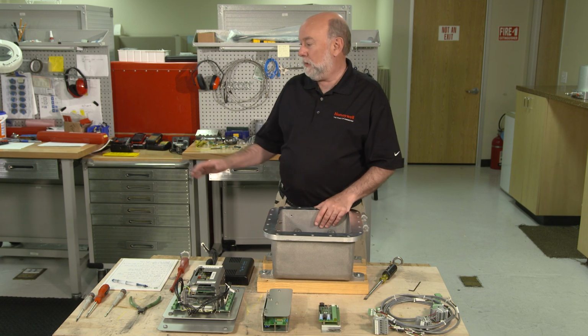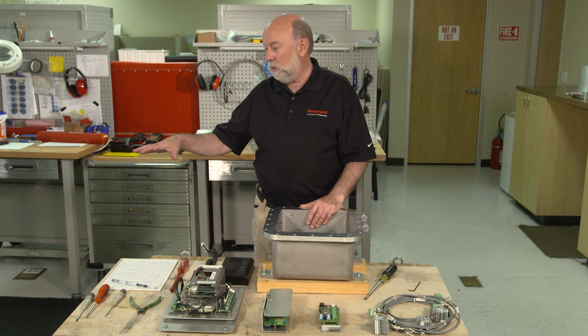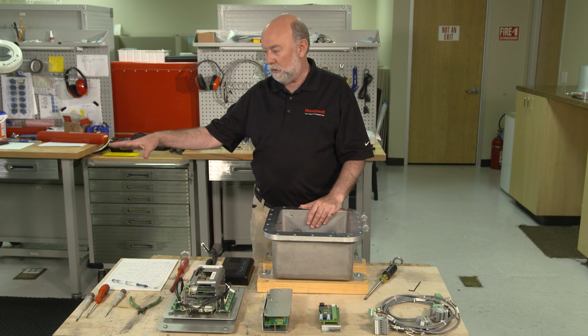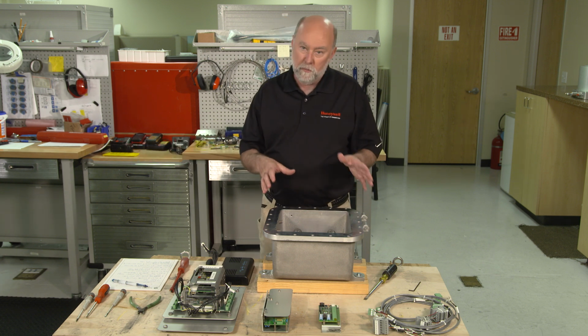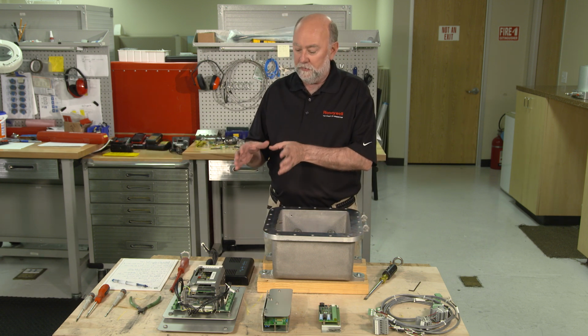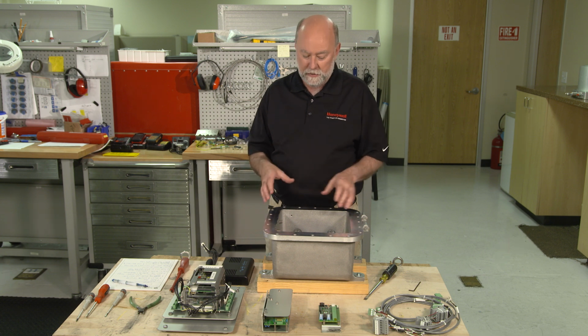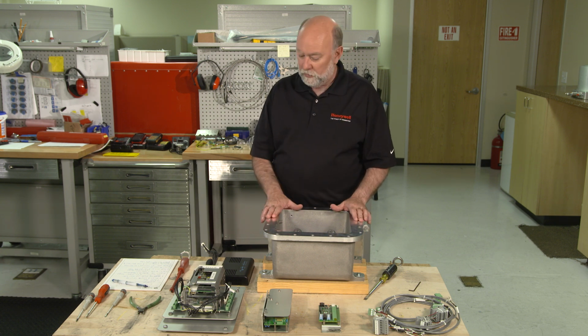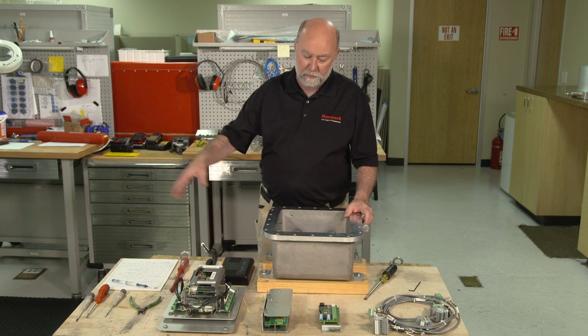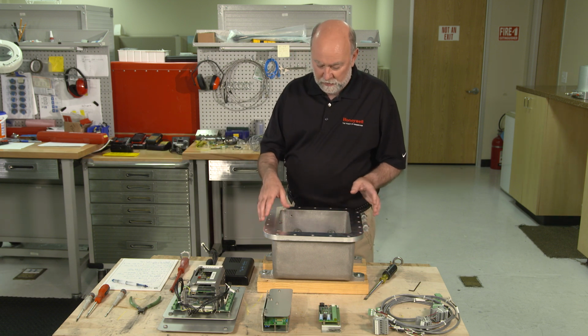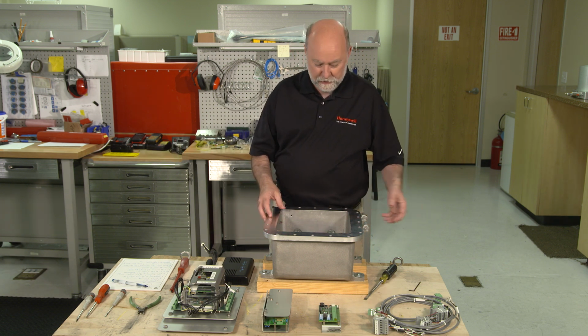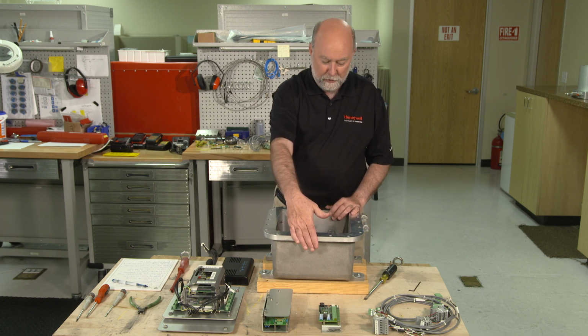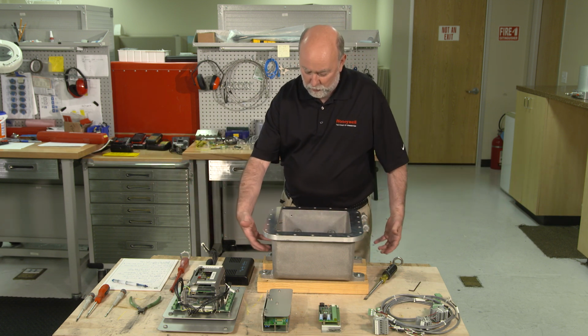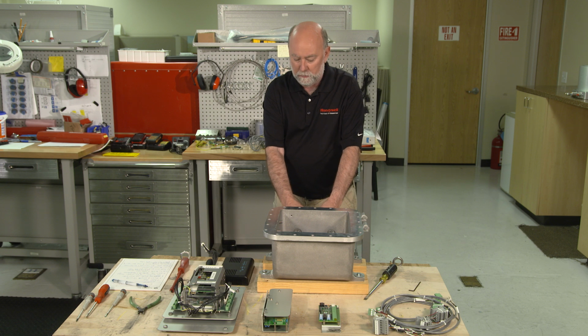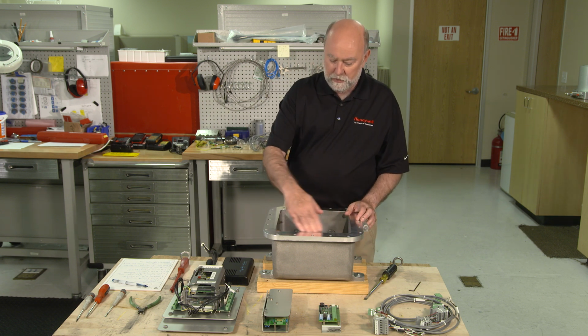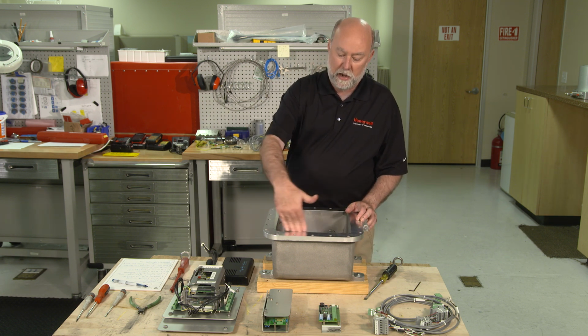So, having completed the disassembly of the older equipment from our junction box, our outlet box on our meter, I want to move on to the assembly of the new equipment, the Series 6 upgrade kit, into that same outlet box. For convenience, we've taken a box that's not mounted on a meter, so it's easier for me to work on here. And just to establish our orientation, I'm looking at the box. The top is here. Transducer cables come in the left and the right. The customer's wiring comes in from the bottom side over here where I'm standing. The DIN rail inside here is at the head of the box right here.